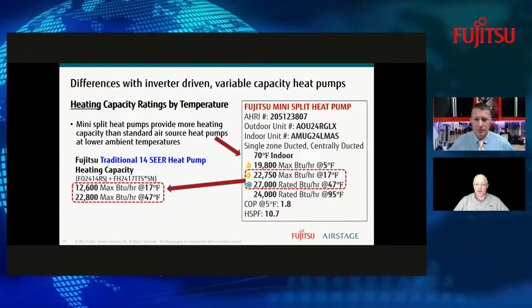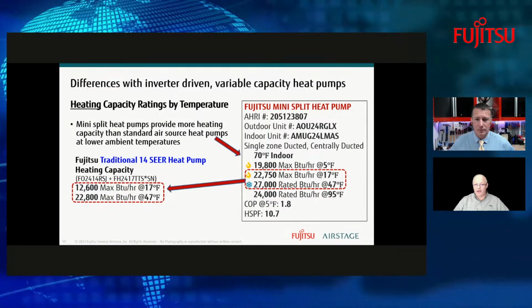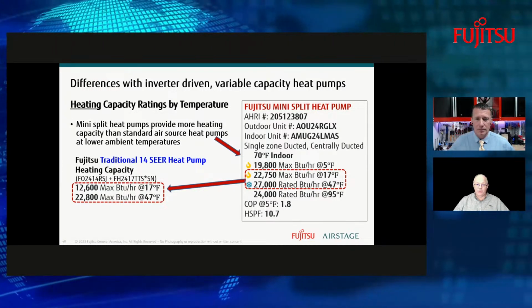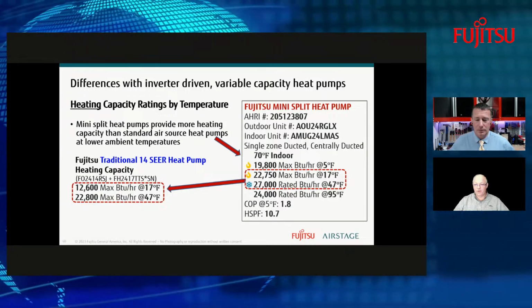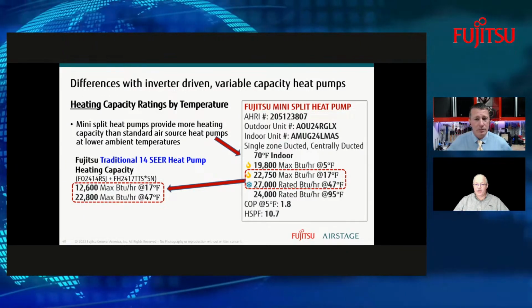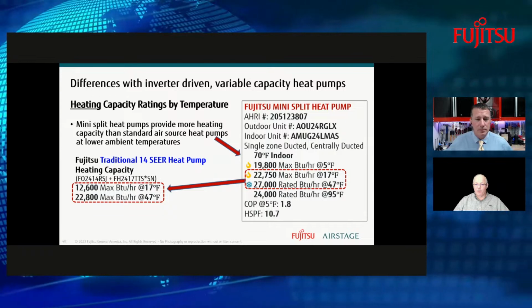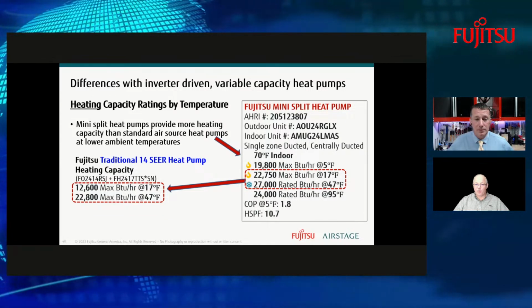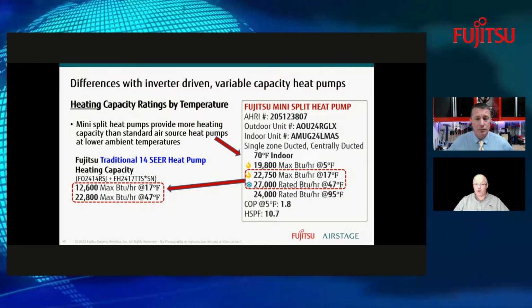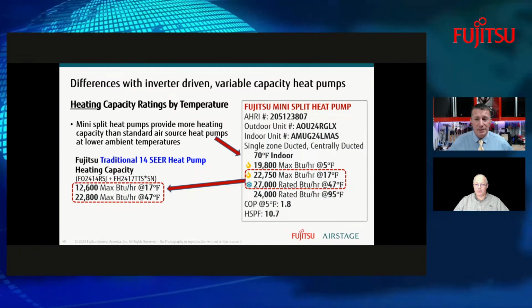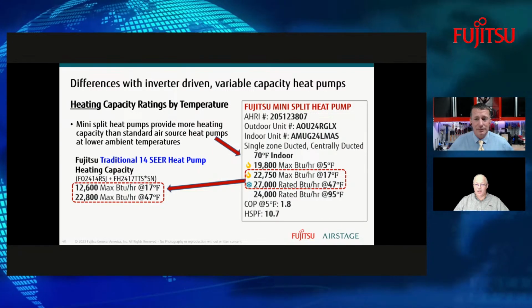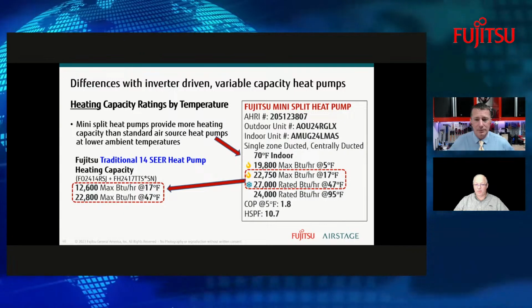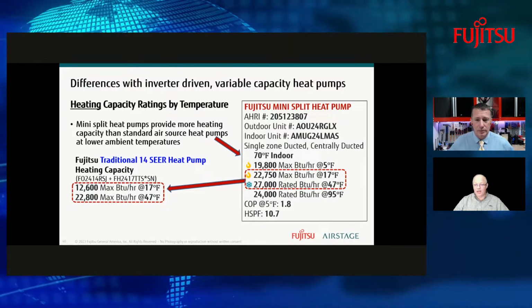The traditional is on the left, the mini split on the right. This happens to be one of our 2-ton traditionals on the left and our 2-ton mini split. When you look at 17 degrees outside, we are providing 10,000 more BTUs of heat with our mini split than we are with our traditional heat pump. Yeah, it's pretty significant. That's a lot. Now, when you get to 47, they're a little bit closer. You know, we have more heat in the atmosphere.